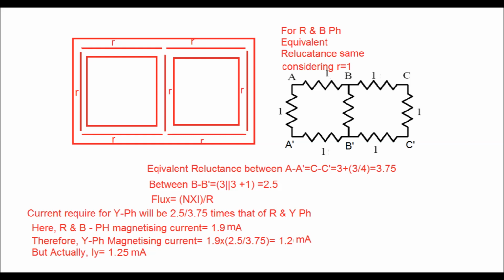Now flux is equal to Ni by R, and the flux is the same for all the phases. So the Y phase will require less current, in the ratio 2.5 by 3.75 compared to red and blue phase. Here the red phase magnetizing current is 1.9 milliampere and the blue phase is 1.89 milliampere. Considering the same for red and blue phase, the Y phase magnetizing current will be 1.9 into 2.5 by 3.75, which comes as 1.2 milliampere. The actually measured Y phase magnetizing current is Iy equal to 1.25 milliampere. That is the theory for magnetizing current for a 3-phase power transformer.